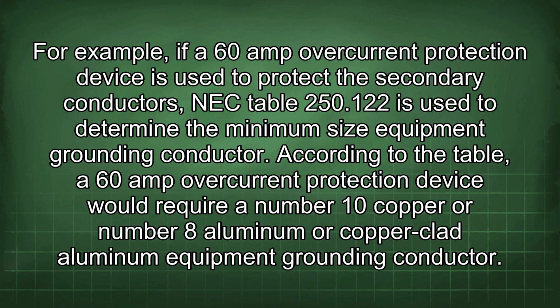For example, if a 60 amp overcurrent protection device is used to protect the secondary conductors, NEC Table 250.122 is used to determine the minimum size equipment grounding conductor. According to the table, a 60 amp overcurrent protection device would require a number 10 copper or number 8 aluminum or copper-clad aluminum equipment grounding conductor.